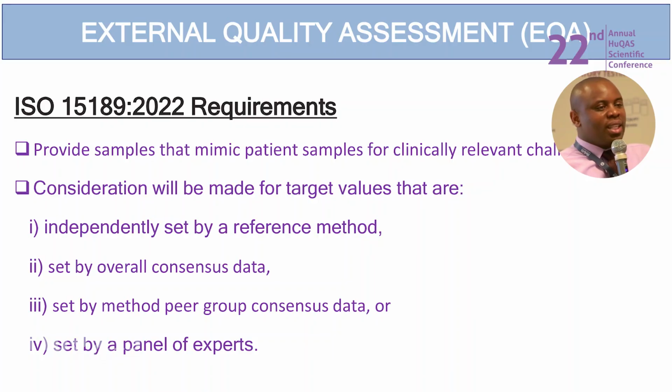Then as we continue with the EQA requirements as guided by ISO 15189:2022, as I conclude, these samples, just like we said for IQC, should mimic patient samples as much as possible, or should have the same matrix as what you'd have for patient samples. Again, to ensure that you are challenging your equipment the way it would be challenged by patient samples.